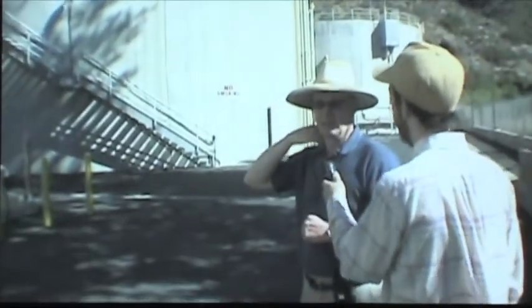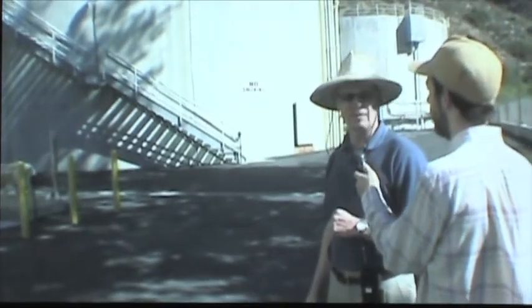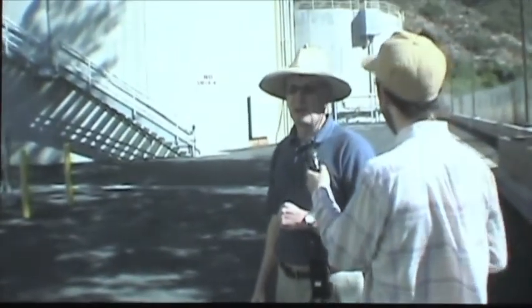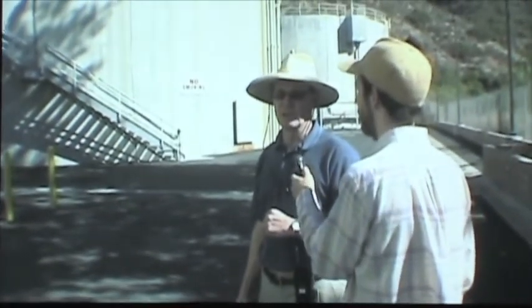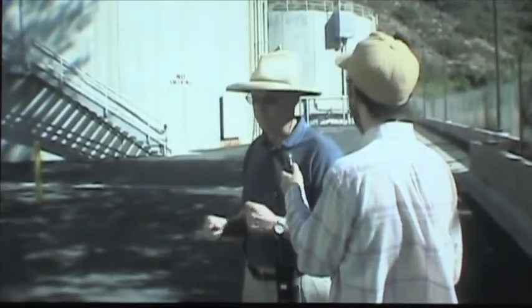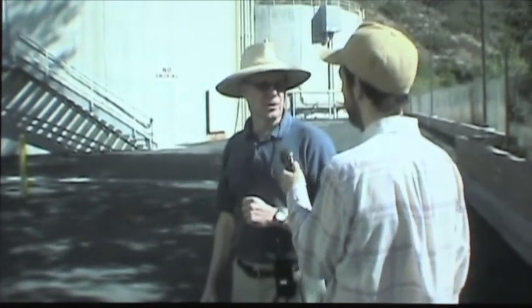Well, yeah, exactly. So it's just being burnt to atmosphere, but it's a source of 400 to maybe 500 kW, which is pretty significant here. That represents probably 40% of the load during most times as it's stretched out over a 24-hour day. And so we'll be able to tap into that resource and use that.